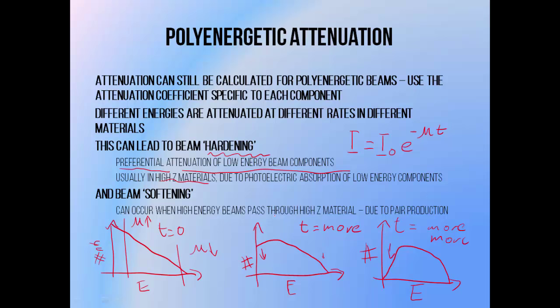Beam hardening usually occurs in high atomic number materials due to photoelectric interactions, since photoelectric interactions are more likely when photon energies are low and the atomic number of the material is high. So when a beam passes through a high atomic number material, its lower-energy components become very likely to undergo the photoelectric interaction and disappear at a higher rate than higher-energy components, which tend to undergo Compton interactions instead — the likelihood of which doesn't increase for high atomic number materials.